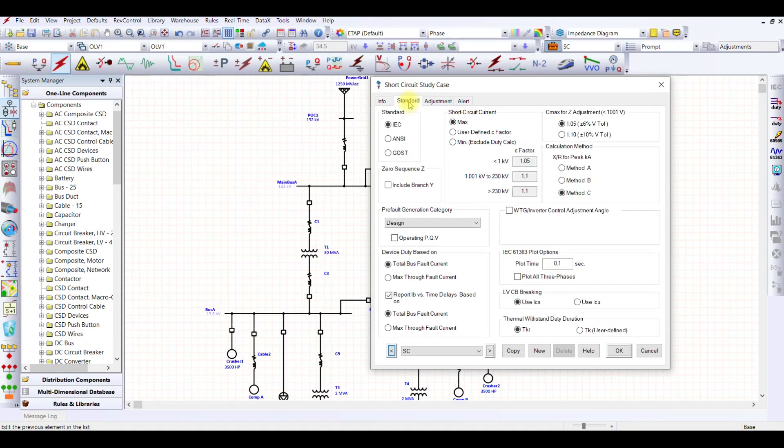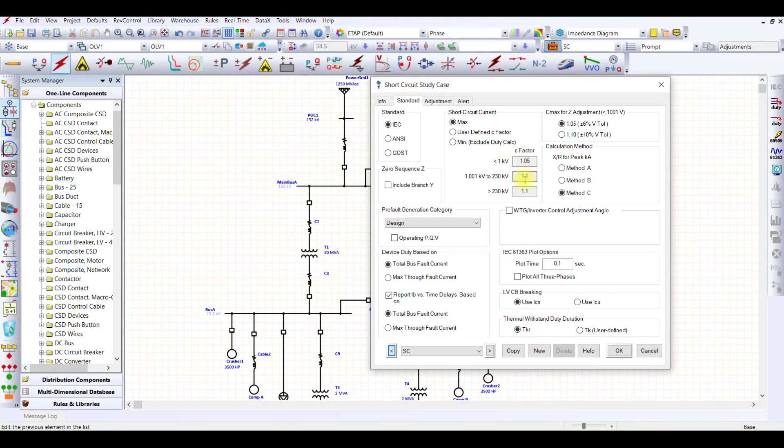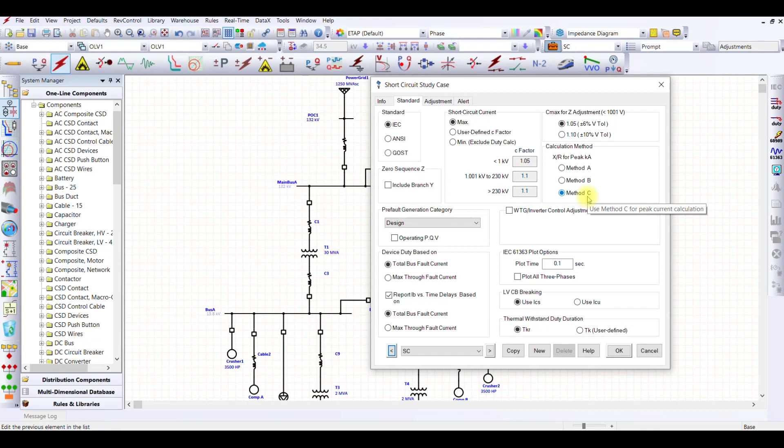Similarly, the standard. If you see in my ETAP 19.1, I have three types of standards: this IEC standard, ANSI standard, and GOST standard. Because we discussed IEC standards, I will be performing using IEC 60909 standard. So what I am interested in, I am in maximum short circuit, so I am going to select maximum short circuit. What will happen in maximum? The C factor is going to be considered as 1.1 for the medium and HV buses. So C max for Z adjustment. Do I have adjustment? I am not taking any adjustment. And the calculation method for X by R for peak kilo ampere, I am using method C.